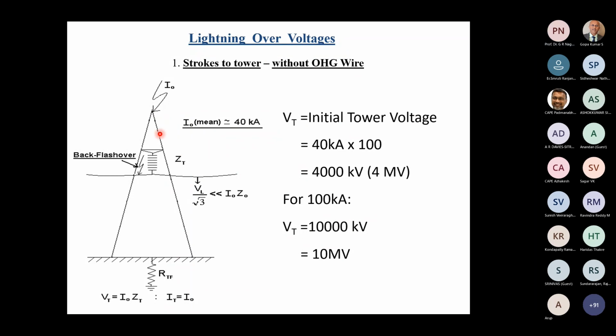Now, if the surge impedance is taken as 100 ohms, that's the lower end of the surge impedance of the tower, you will find that the tower voltage would be 40 kA multiplied by surge impedance, 4,000 kilovolts or 4 million volts. The tower becomes a high voltage object at 4 million volts. The phase conductor is only at the system voltage. For example, if it is 220 kV, its phase conductor will be only about 180, 190 kV.